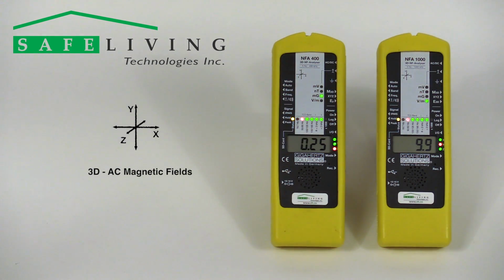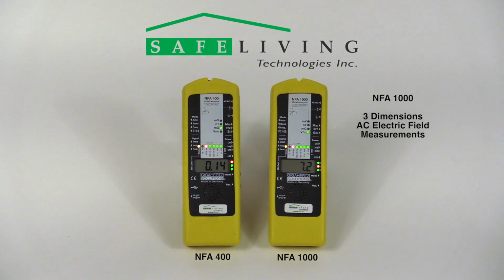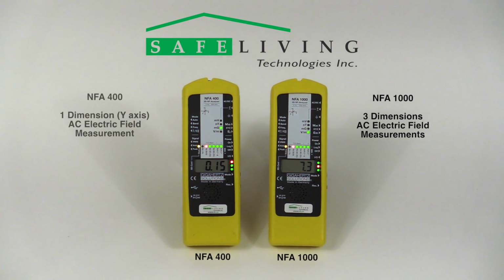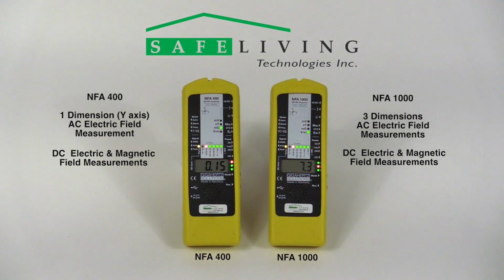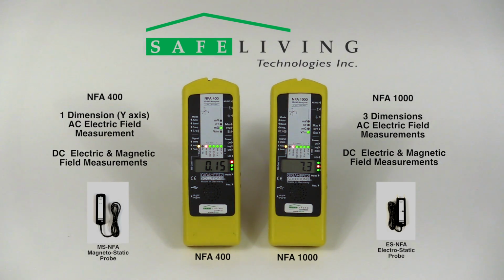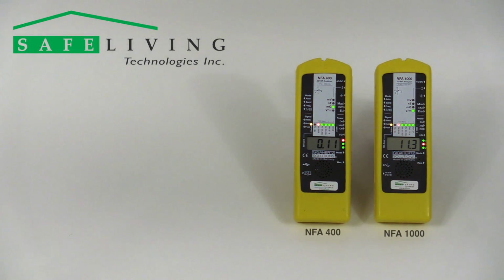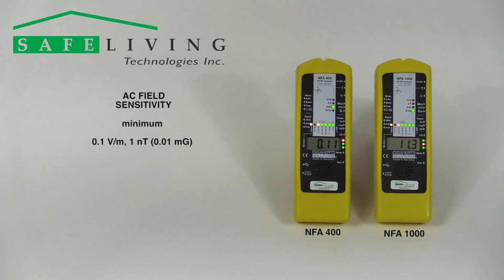Both meters measure AC magnetic fields in 3 dimensions on the X, Y, and Z axis simultaneously. The NFA1000 can measure AC electric fields in 3 dimensions, and the NFA400 measures AC electric fields in 1 dimension on the Y-axis. The NFA400 and NFA1000 can also measure DC electric and magnetic fields with optional accessories such as the magnetostatic and electrostatic probes. The NFA1000 and NFA400 offer excellent sensitivity down to 0.1 volts per meter for AC electric fields or 1 nanotesla, which is 0.01 milligauss for AC magnetic fields.